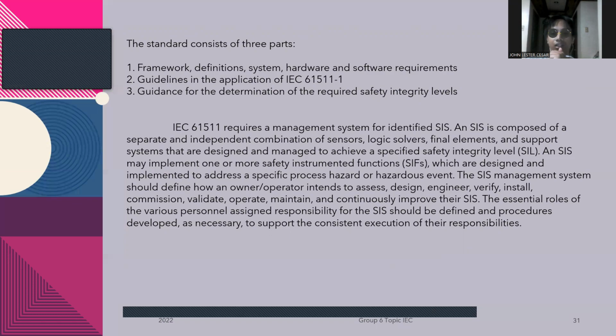hazard or hazardous event. The SIS management system should define how an owner or an operator intends to assess, design, engineer, verify, install, commission, validate, operate, maintain, and continuously improve their SIS. The essential role of the various personnel assigned responsibility for the SIS should be defined and procedures developed as necessary to support the consistent execution of their responsibilities.